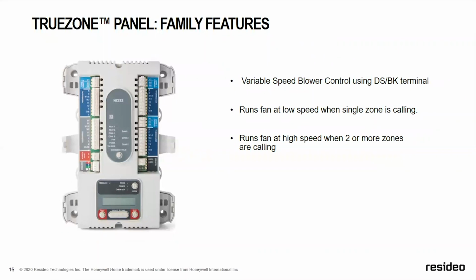We also have variable speed control. Now you have to have a furnace that has 2 speeds available. I'm not going to mention brand names, but typically if you see a dehumidification terminal on a computer board for a furnace, that's where you would use this terminal. It is a 24-volt output, and it'll run the fan on low speed when only one zone is calling. It runs the fan on high speed when 2 or more are calling.